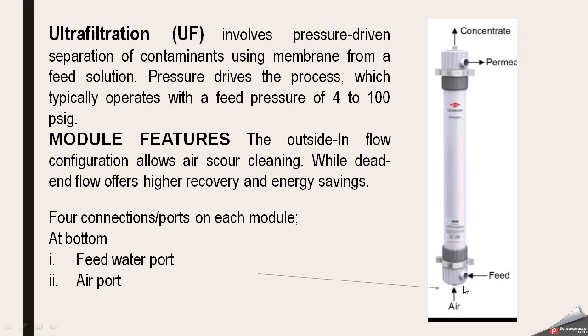This is the typical module of a UF membrane in which water flows. The water outside-in flow pattern configuration allows air scour cleaning, while dead-end flow offers high recovery and energy saving. In this module, water flows from outside to inside the membrane, allowing better air cleaning.